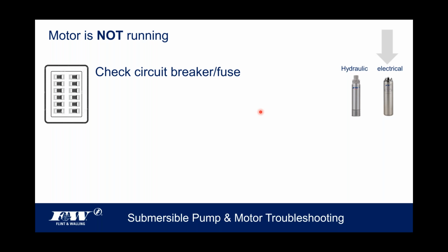The motor's not running. So some things to check if the motor's not running. I'm looking at the clock. I'm at about 17 minutes, so I'm hoping to get through the rest of these slides before that time comes up. Obviously, the first and easy thing to do, if the motor's not running, is to make sure we've got power going to the motor. If there's a circuit breaker or a fuse that's blown, obviously that's the reason the motor's not running.